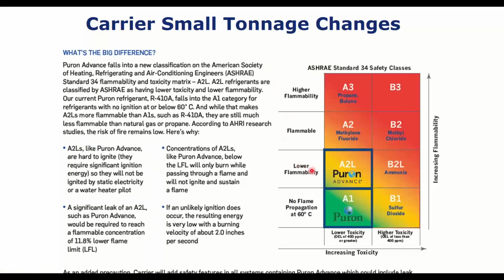As mentioned, the flammability is the big difference, and it'll probably say it right here: these A2Ls are difficult to ignite. They require a lot of energy, so they're not going to light accidentally. Examples given were a pilot light or static electricity igniting it—that won't be enough energy. You'll need more energy than that to ignite it, so it's not likely you'll have an issue.